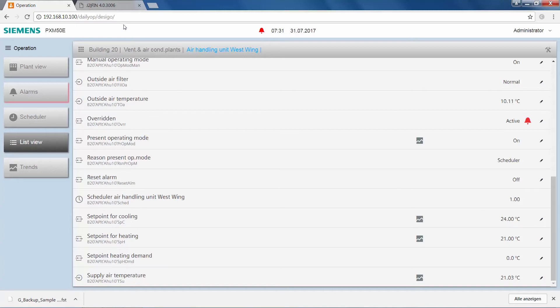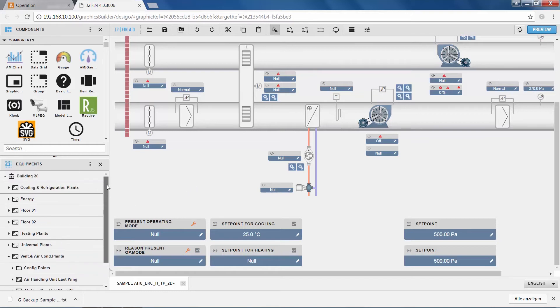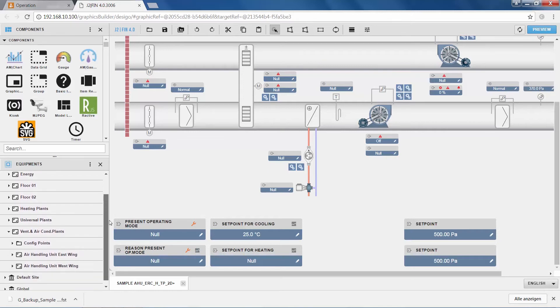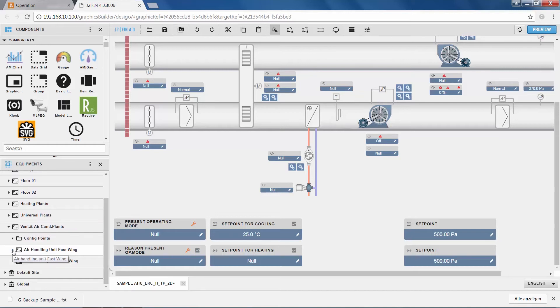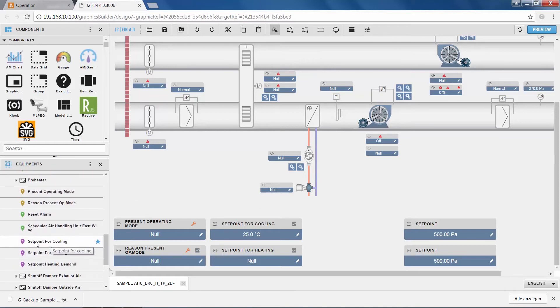Now in order to actually define the binding, we go back to the graphics editor tab, where we still have the air handling unit graphic open. The straightforward way to make a binding from a data point to a component in the graphic is via the equipment tab, where we can see all the data from the system. We navigate to the east wing air handling unit, look up the cooling set point, grab it, and drag and drop it onto the label for the cooling set point, by which a binding is created in the background. However, as we have pulled the set point for cooling from the east wing air handling unit's data structure, this binding is now absolute.